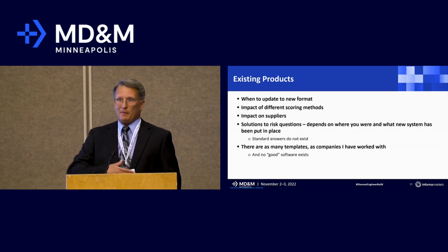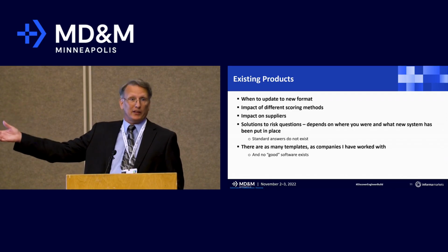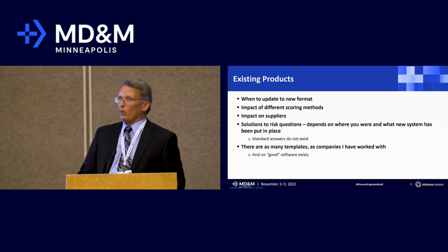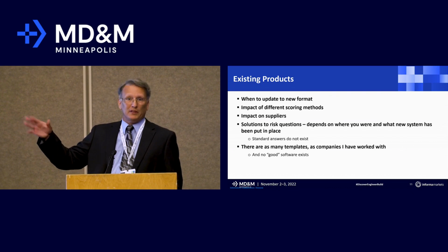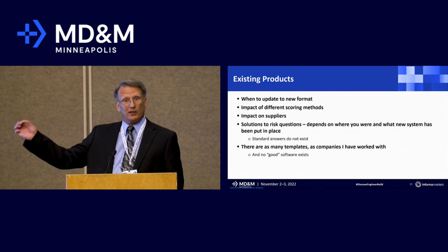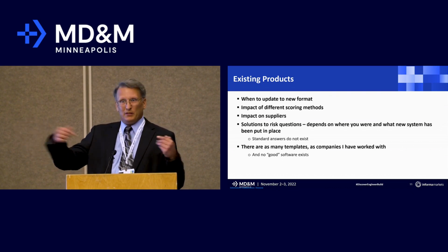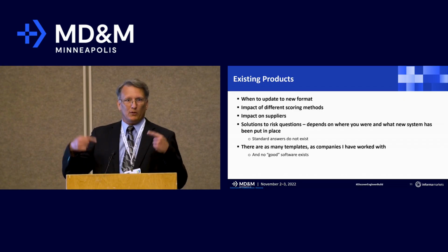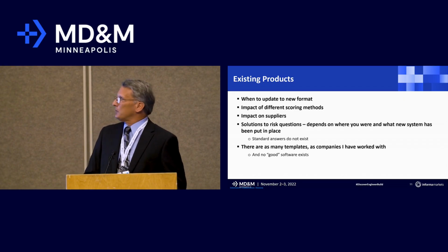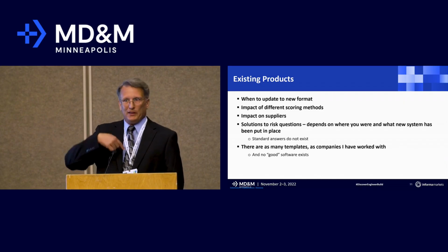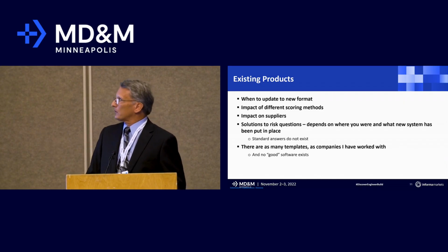You don't want to just automatically go change everything. What if you never build it again? Or what if it's low volume? Or what if it's just stable and never has any changes? State-of-the-art could change. So you could have a state-of-the-art review, but you don't necessarily have to create brand new documentation. So what's your criteria for when to update existing products?